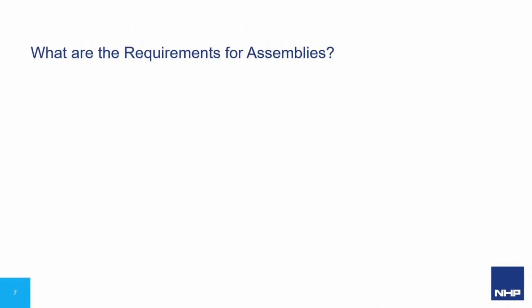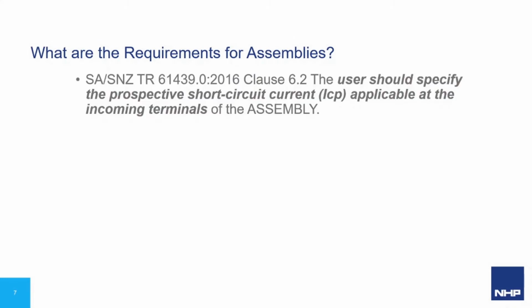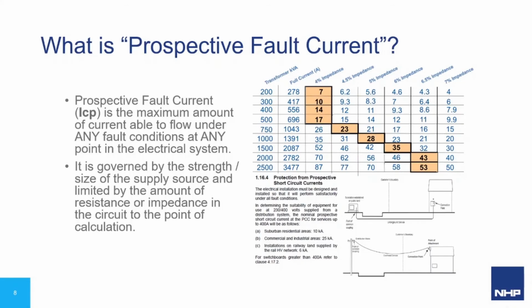So what are the requirements of the assemblies? The first critical piece of information required is the end user or someone acting on their behalf must specify the maximum fault level that may occur where an assembly is to be installed. When specifying this, we're talking about the prospective fault current. So the end user must define the prospective fault current, which is derived from the strength of the supply source to deliver current under a short circuit condition of negligible impedance across all three phases.